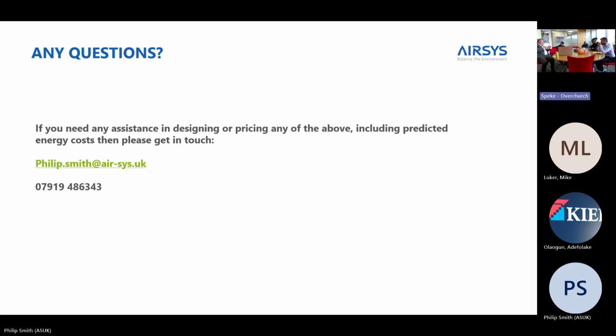The only time we've had issues with humidity is where the client has a precise RH requirement, and that's typically only in clean rooms or standards rooms where they want 30% RH to manufacture their powders. And in those instances, a chemical dryer is a much better option in terms of the energy, but you'd have a chemical dryer with some form of cooling, a CRAC unit as a combination, for example.